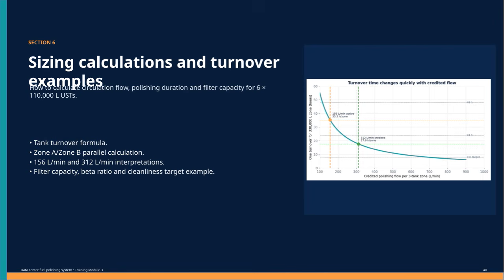I'll walk you through how to calculate the circulation flow, polishing duration, and filter capacity for these tanks. We'll start by reviewing the tank turnover formula, which is essential for understanding how fuel cycles through the system. Then, we'll explore the Zone A and Zone B parallel calculations, which help us optimize the flow distribution between different zones.